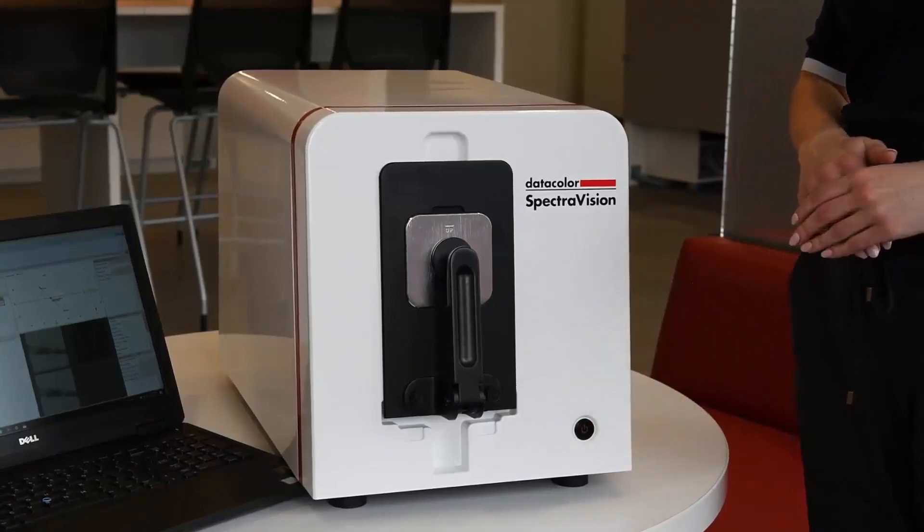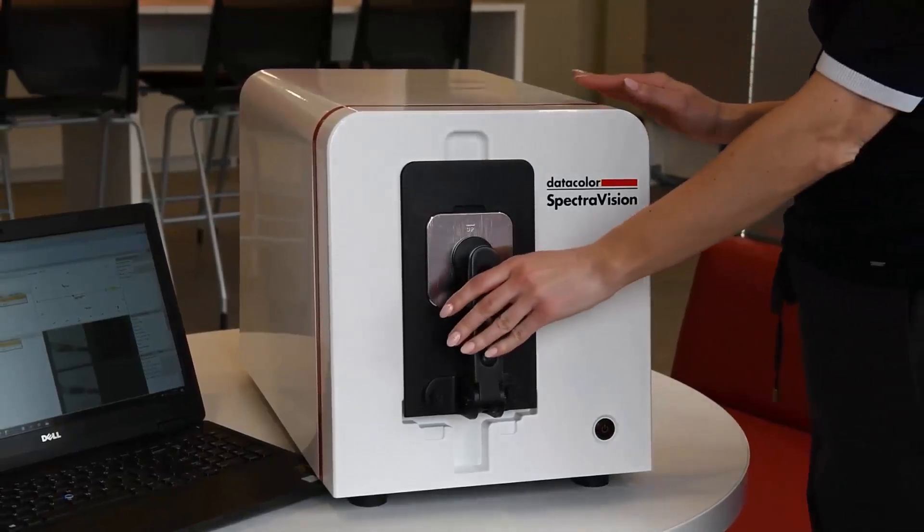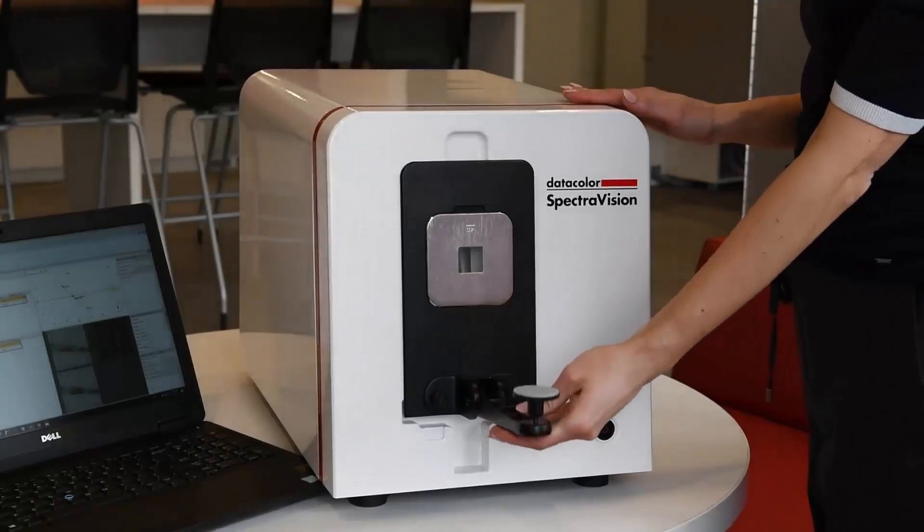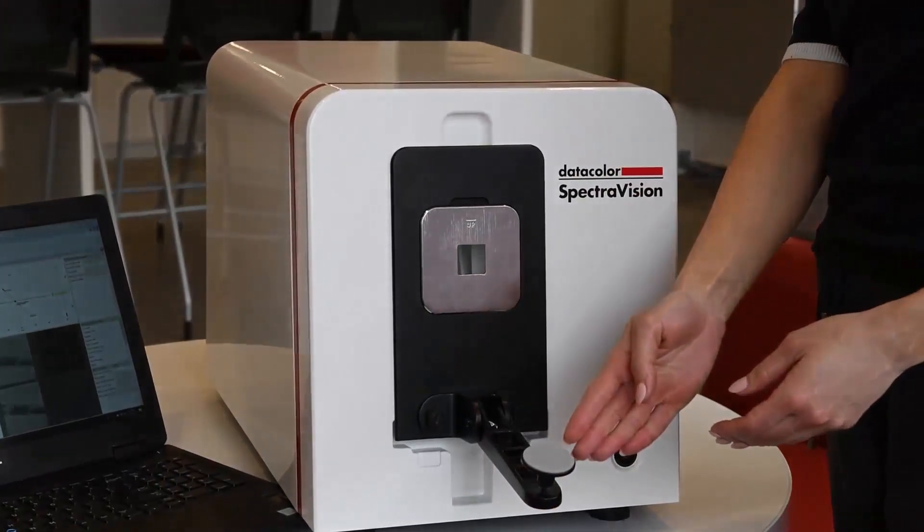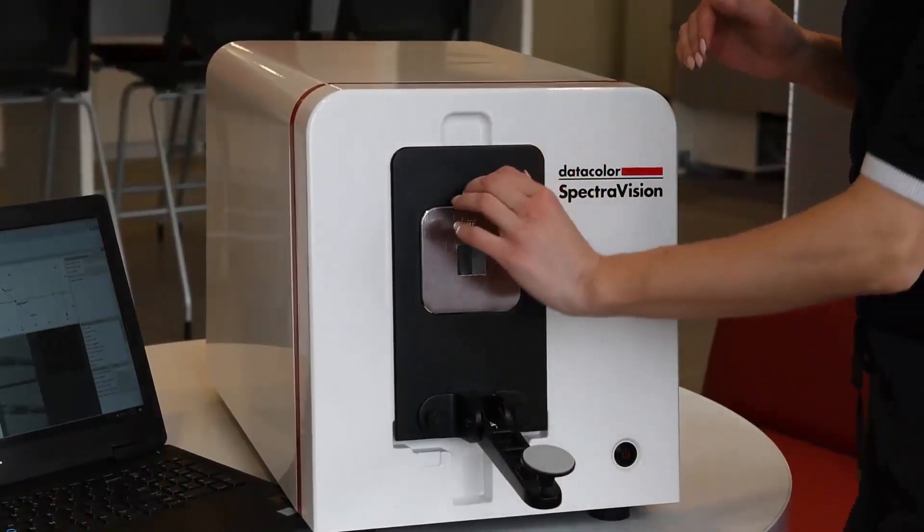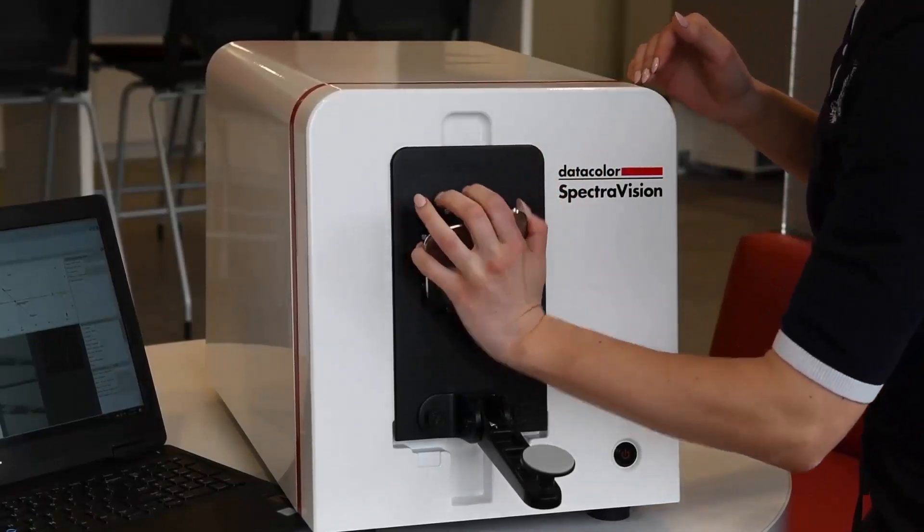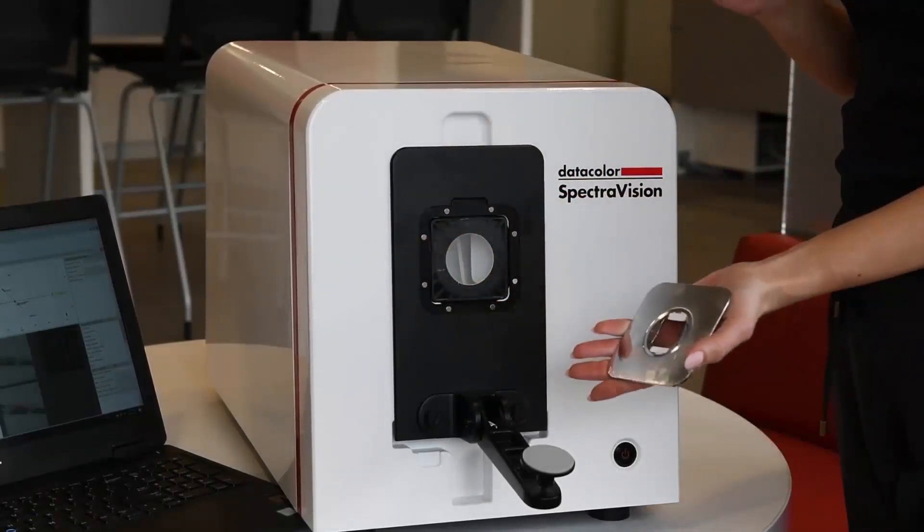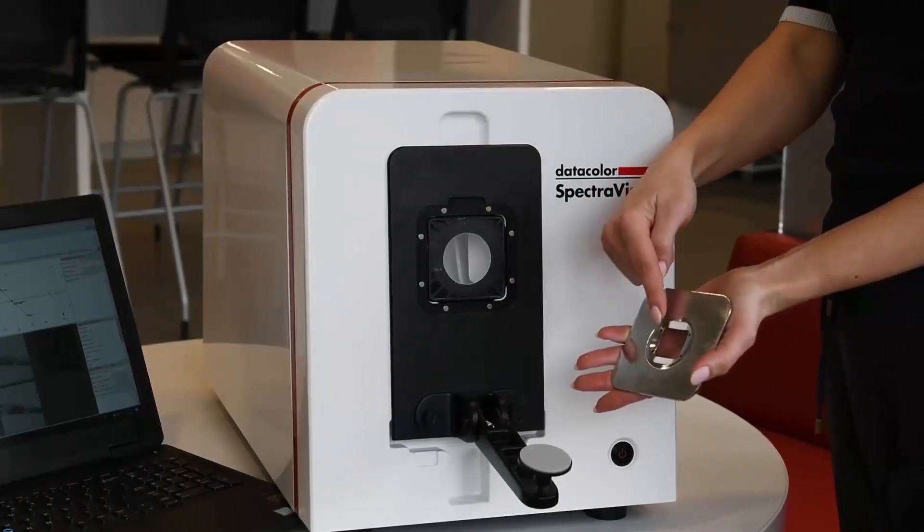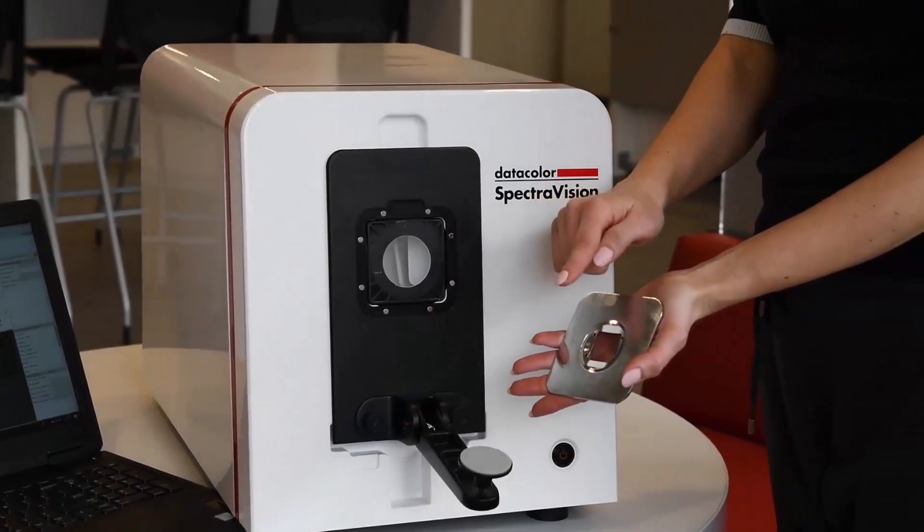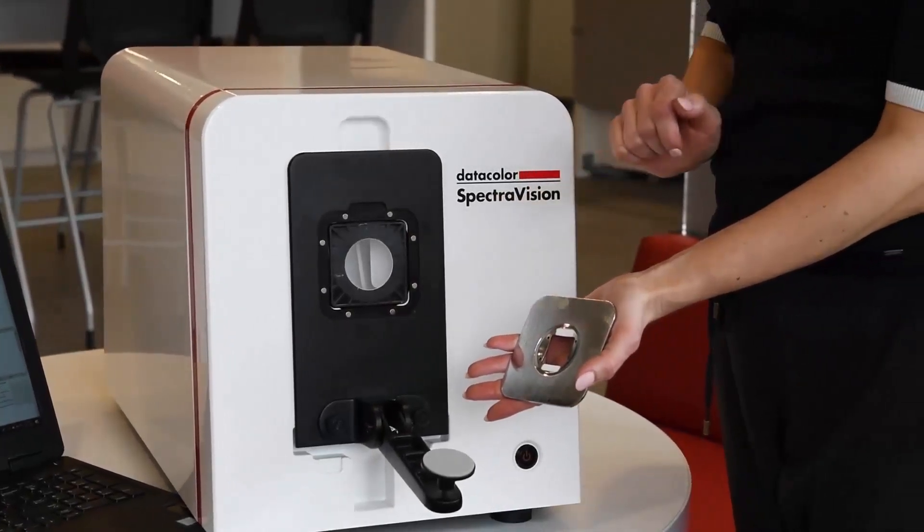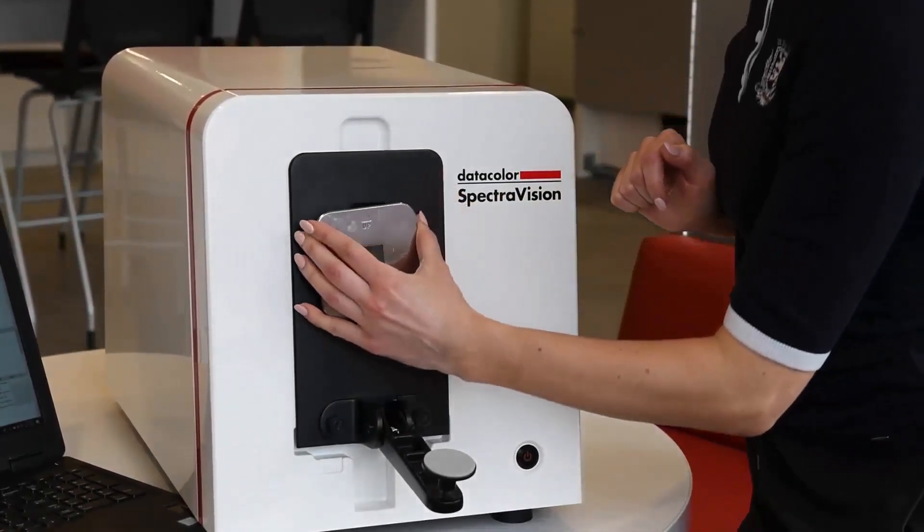This instrument has a similar sample arm attachment as our 800 spectrophotometers. This can be pulled back to view the aperture plate and correctly position the sample. The aperture plate is a square 25.5 millimeter illuminated and 23 millimeter viewed. The aperture plate can be removed but do not touch the inside of the plate. Place the plate back on the unit.